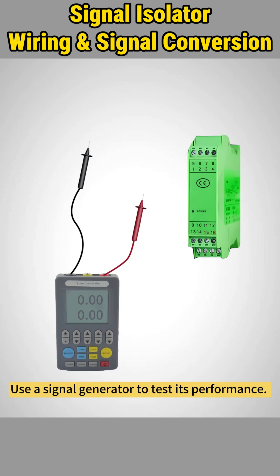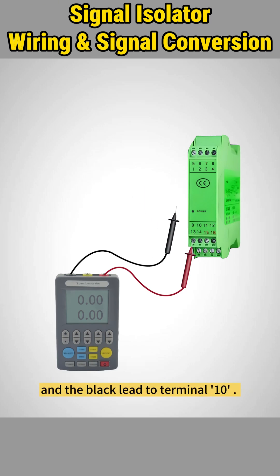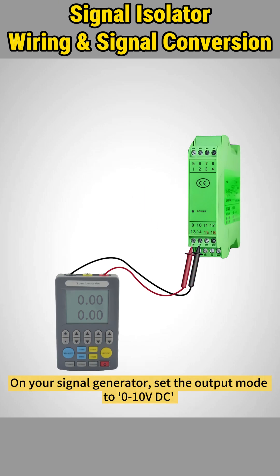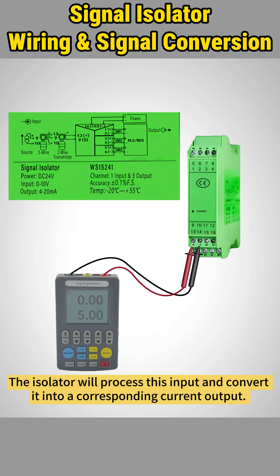Use a signal generator to test its performance. Connect the red lead from the signal generator to terminal 9 and the black lead to terminal 10. On your signal generator, set the output mode to 0 to 10V DC and configure the desired voltage level. The isolator will process this input and convert it into a corresponding current output.